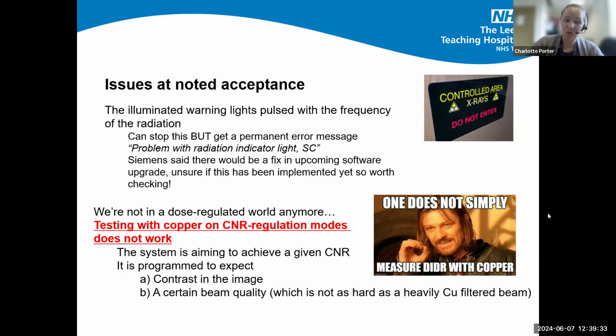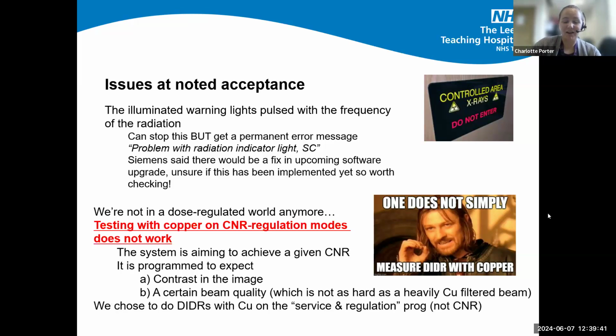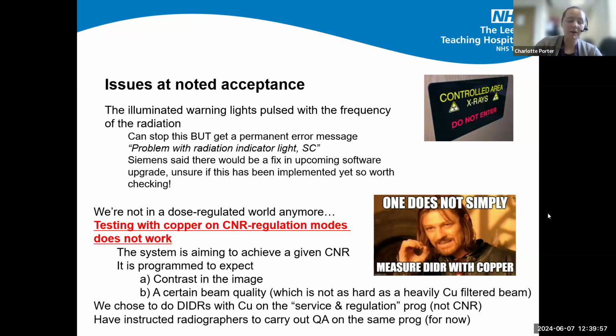So locally, though I'm sure other people might choose to do things differently, we chose to do some of our detector input dose rate testing on the service and regulation program, because that isn't contrast noise regulated. That is the standard dose regulation that we're used to seeing on older Siemens systems. We've also currently instructed our radiographers to carry out their QA on that service and reg program, because the results were just not repeatable with the equipment that they had, which was copper. So for now, that's the route we've decided to go down. I'm sure we'll discuss alternatives in the rest of the webinar.